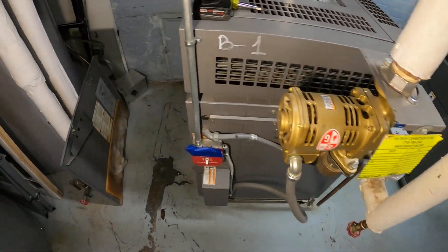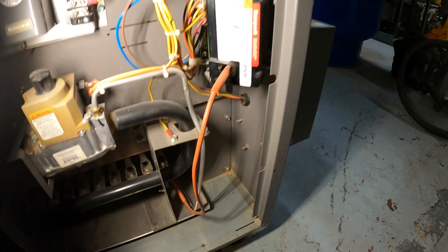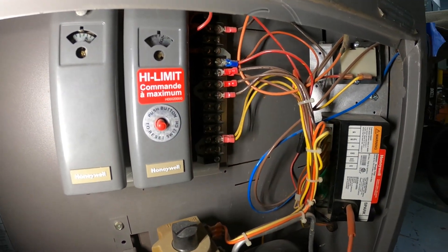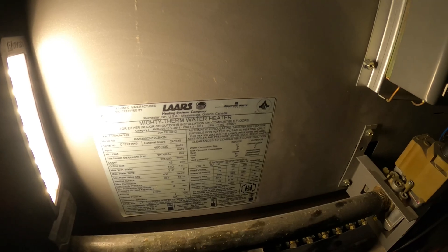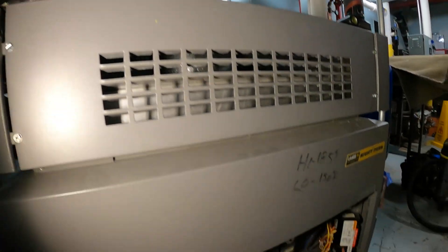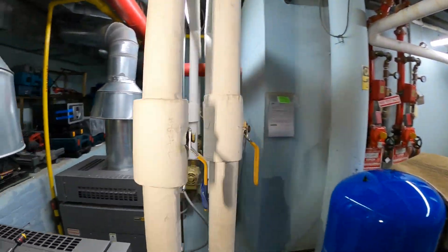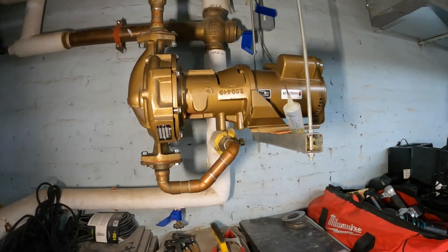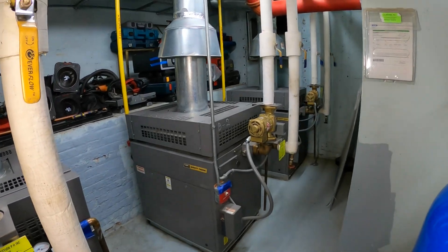I opened up this bottom cover on boiler number one. Currently the power is set to off — the switch is down. Inside, this is the burner section. I can see some dirt build-up back there, so definitely time for maintenance. We have our gas valve and a couple of controls. This is a LAARS Mighty-Therm water heater, used for showers and sinks for nine floors. All three boilers work in conjunction together — they are all piped in together — and there's also a circulating pump booster, even though each unit has its own pump.